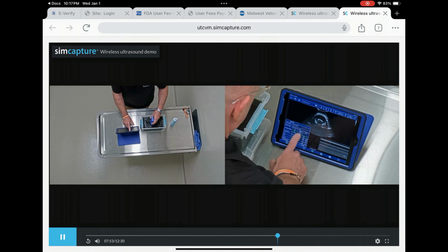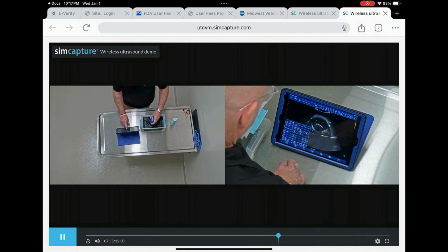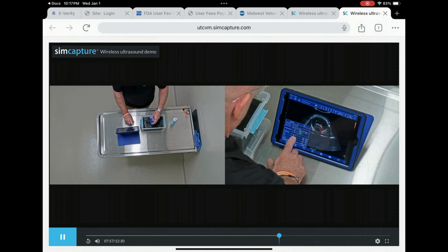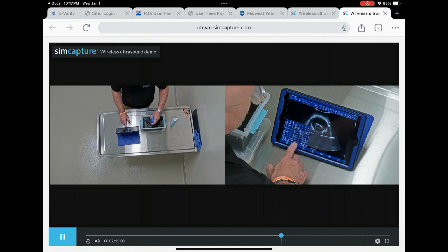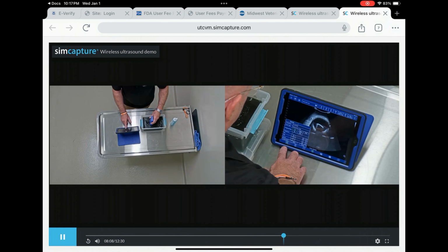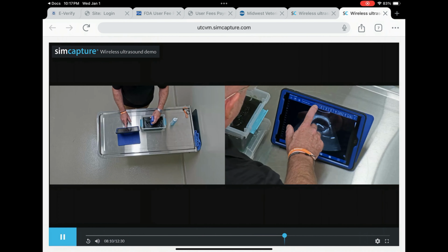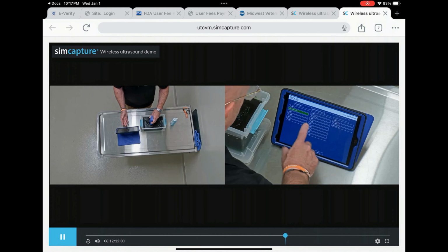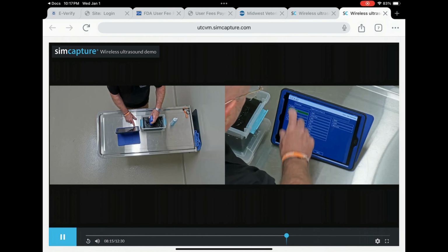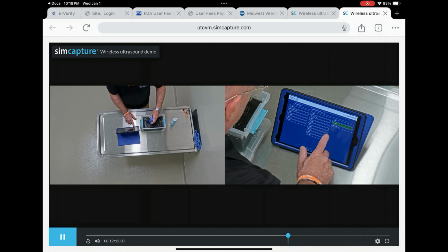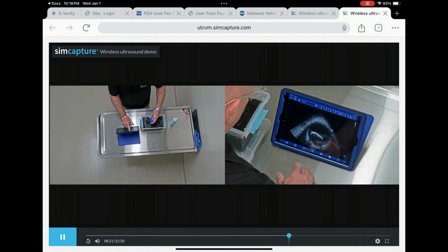We can create any number of presets that we want, any type of label under any of the 3 ultrasound transducers. Here I'm going to select the cardiac function, and now when I'm on the screen, some of you may recognize the phased array sector, and we're still imaging the bladder with the stone, but primarily this feature would be used for cardiac scans. I'll go back to our B mode and select another exam.